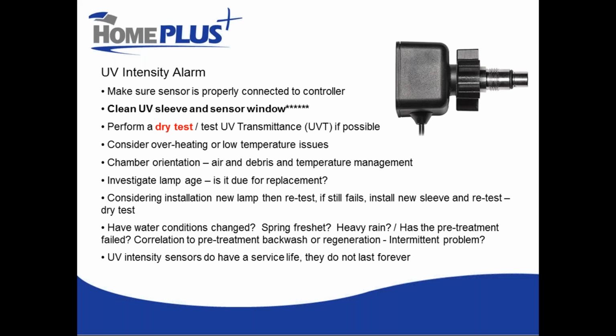Also clean the little glass window on the sensor. That little window, if it has mineral buildup on it, will also block the UV light from reaching the sensor. Once you've done that, you can perform what we refer to as a dry test.